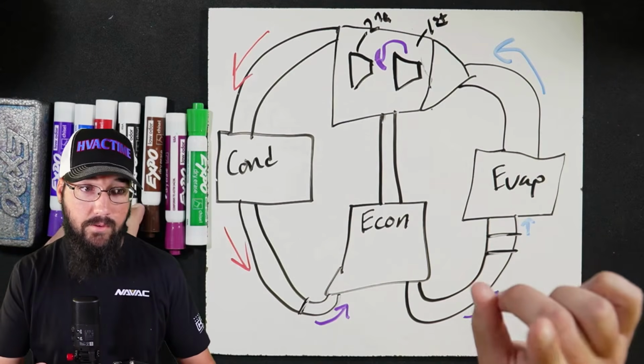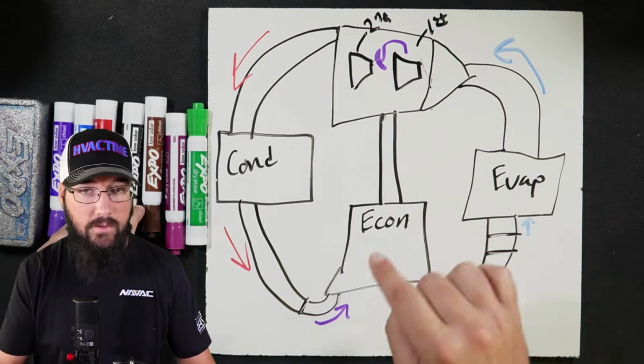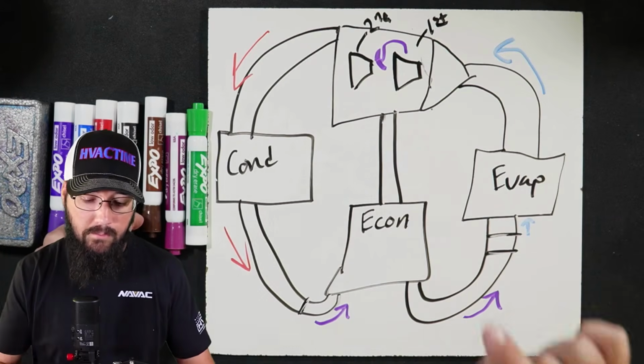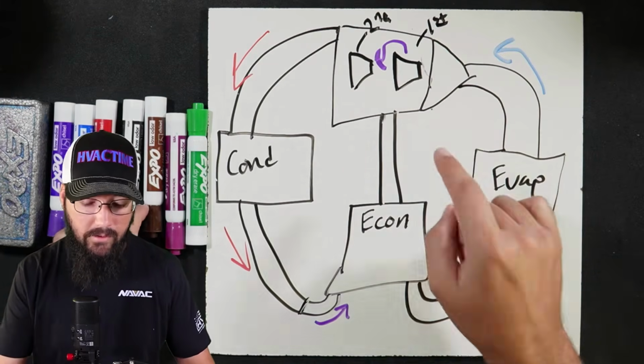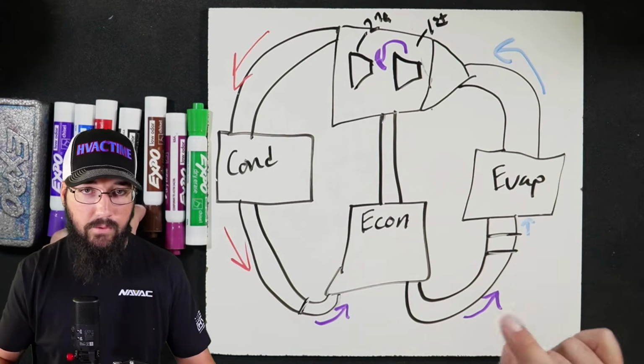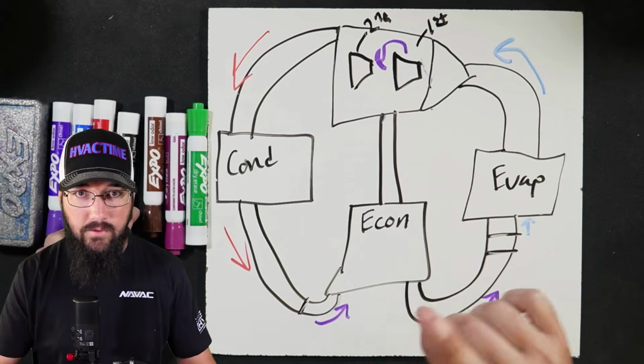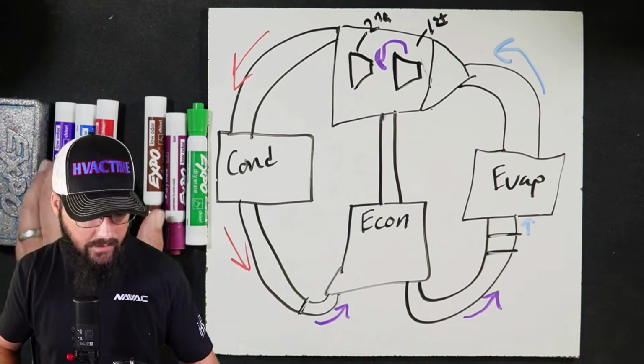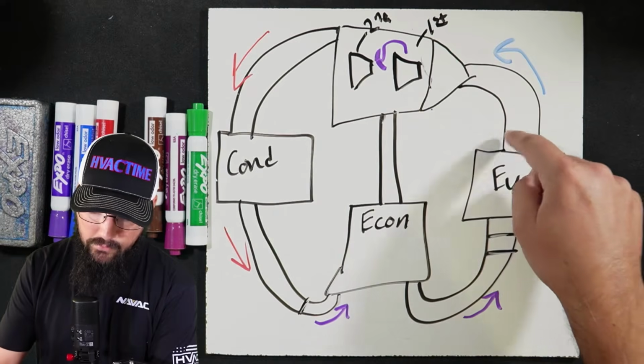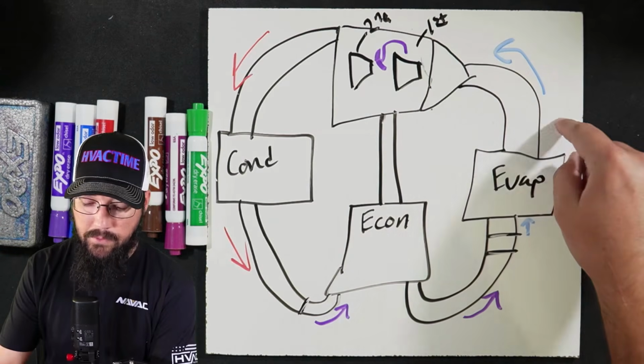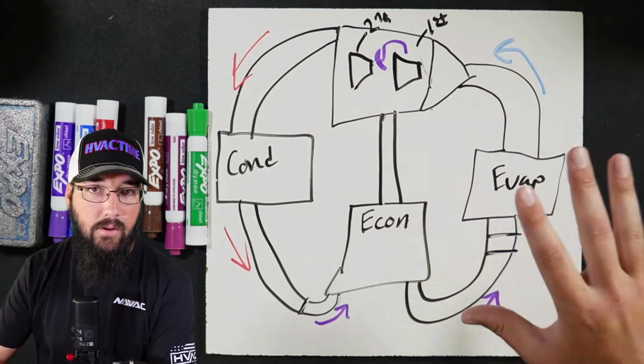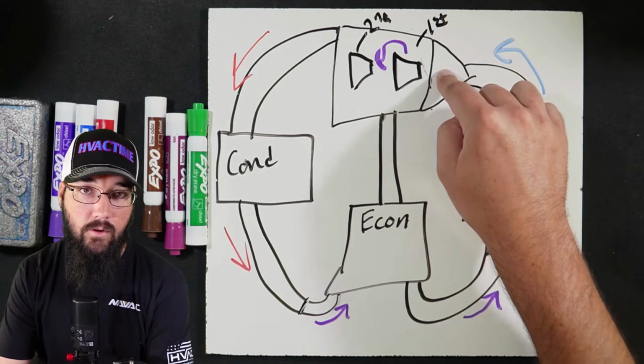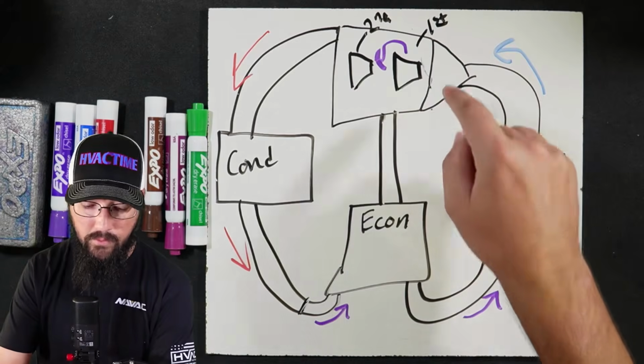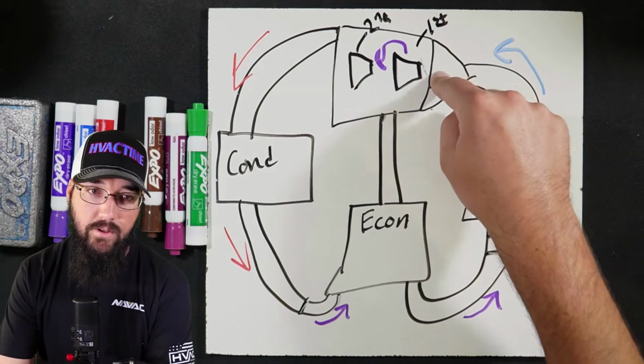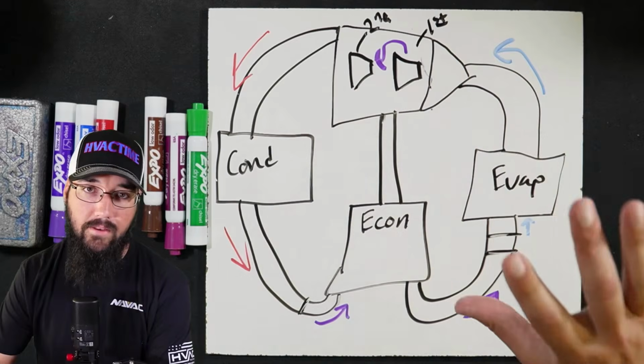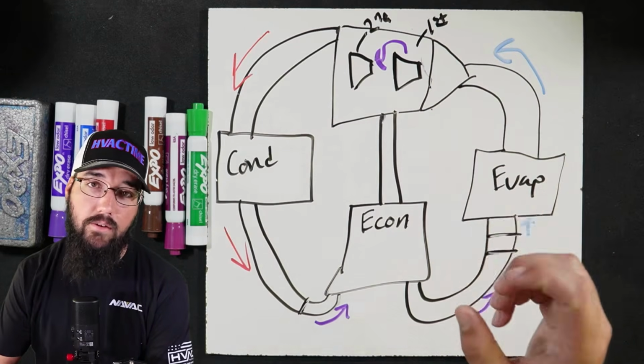This is very important. This is not specific to just Trane. Trane is not the only company that does this. But it's important to understand that to make this work correctly, we need a multi-stage compressor. If it's just one impeller, single stage, this same concept wouldn't work exactly the same. So we have superheated vapor coming off. Now this vapor is going to be 0.5 degree Fahrenheit, 1 degree Fahrenheit superheated coming into our compressor. It sounds really low, but this is normal for centrifugals. We've got a set of guide vanes right here. These guide vanes are controlling the refrigerant flow coming into the front of the impeller.